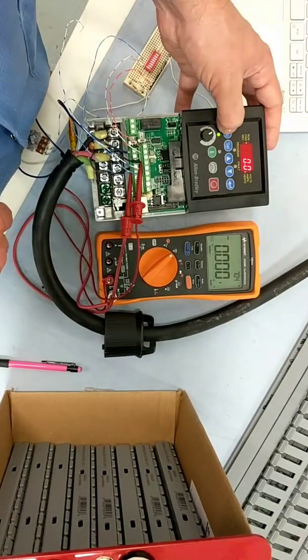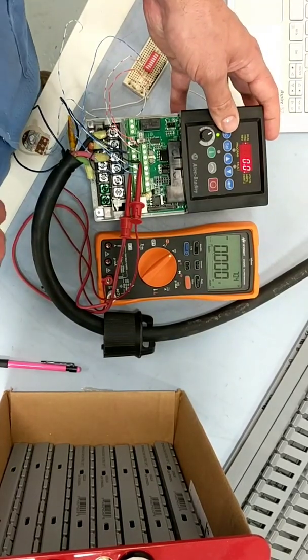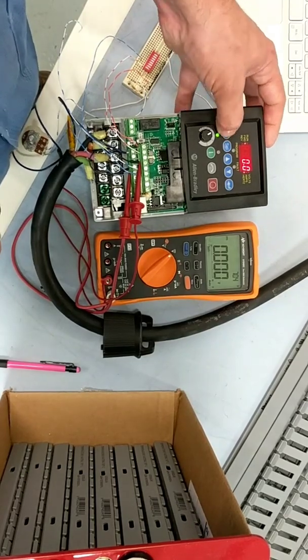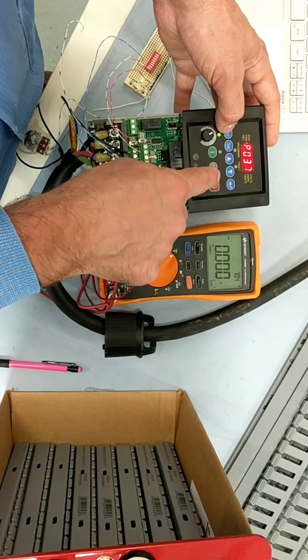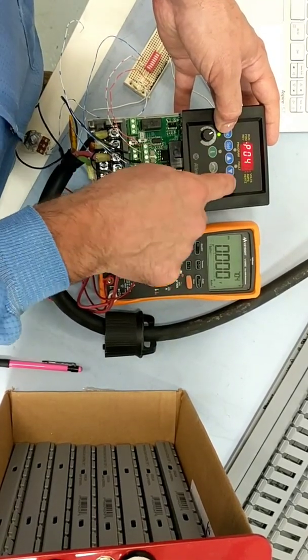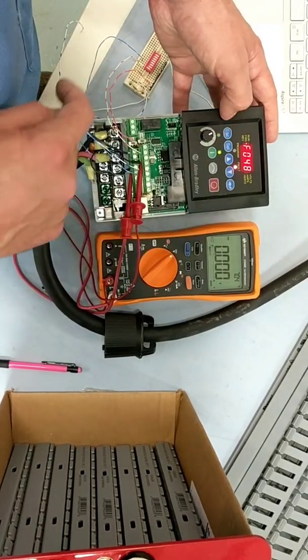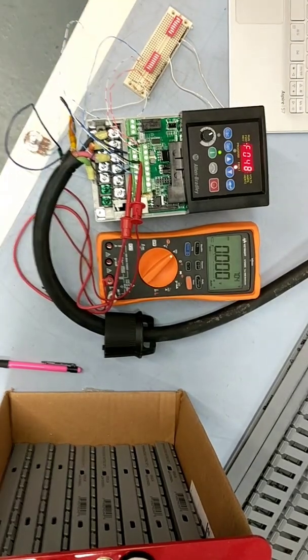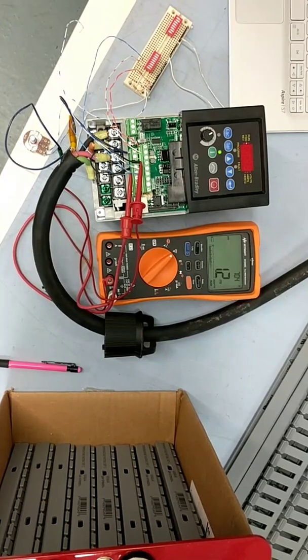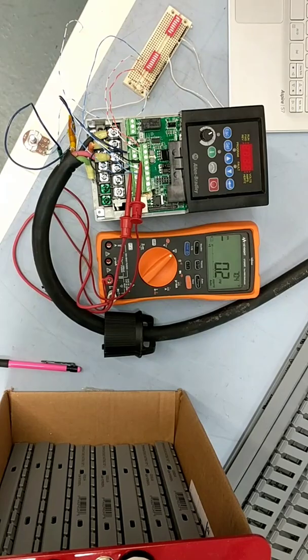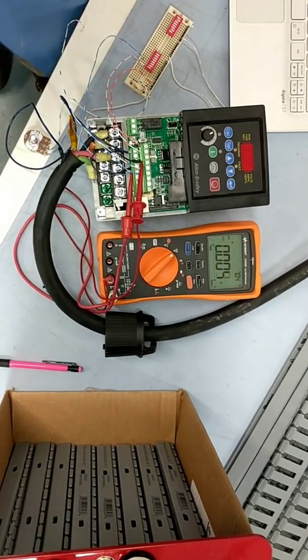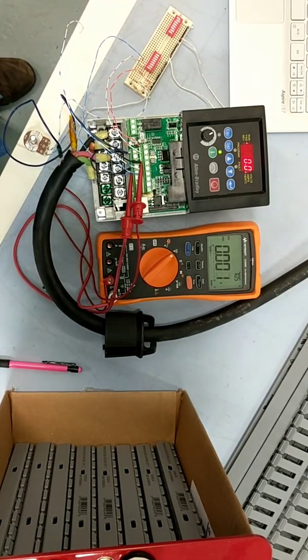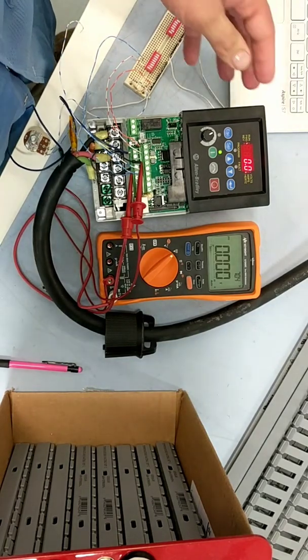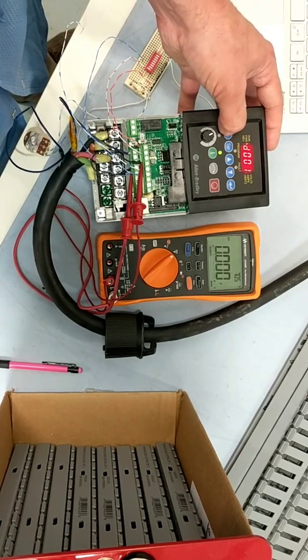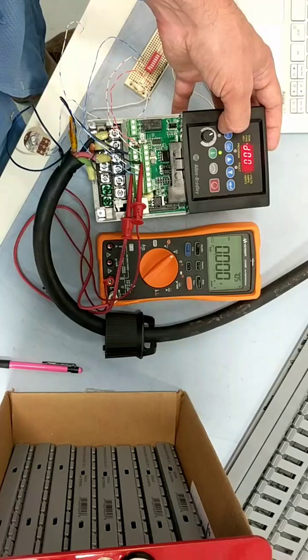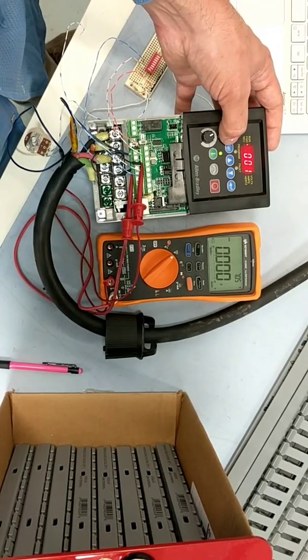If the drive starts up in an unknown state, change parameter P41 to 1 to restore to factory defaults. Gonna have to power cycle. F4 is for low voltage input, or I should say AC voltage input's too low, so it temporarily shows that when it powers down. All right, now we'll be able to set up our parameters. Hit select, hit escape. Escape again if we're not on the right parameter.